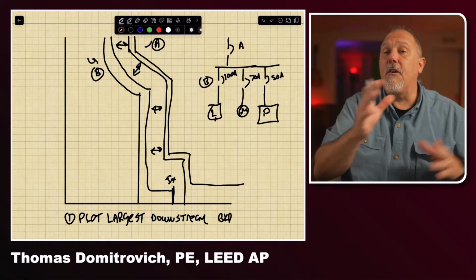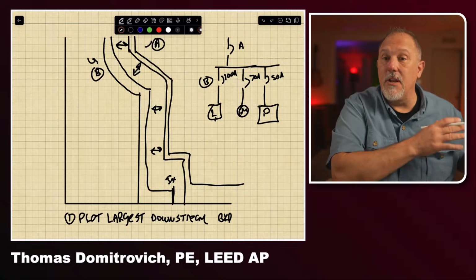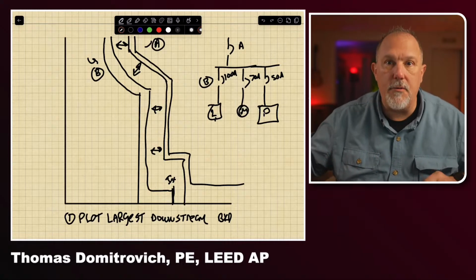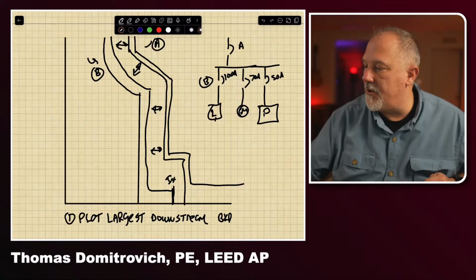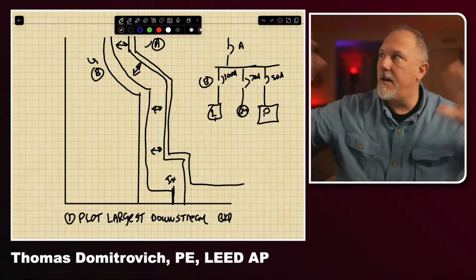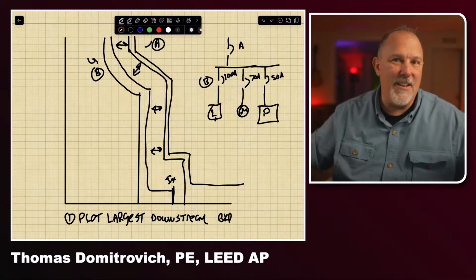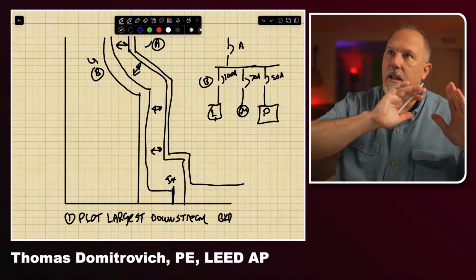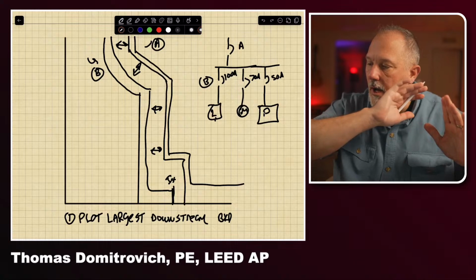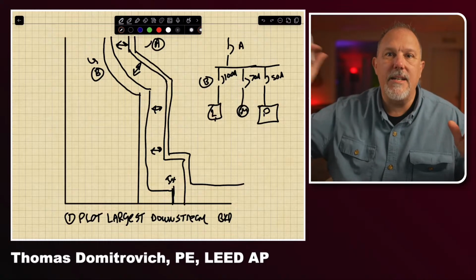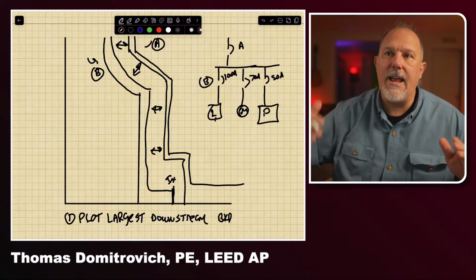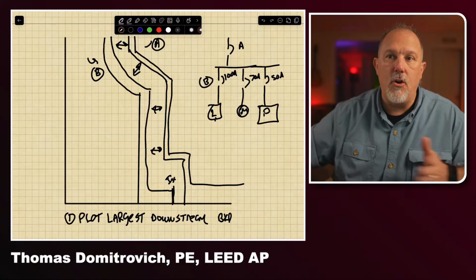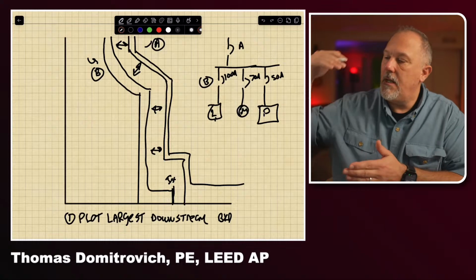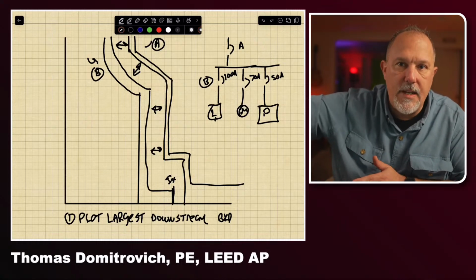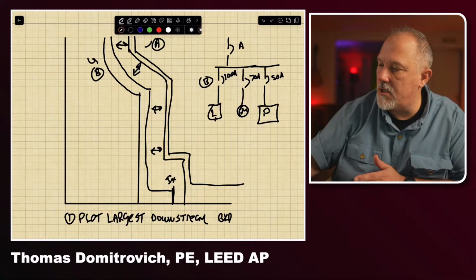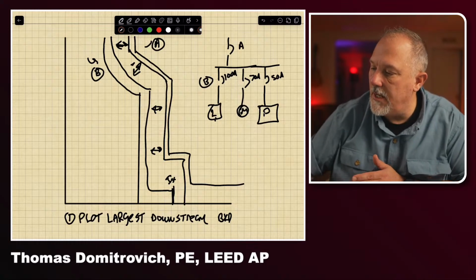Now, for other reasons, you're going to want to take a look at your loads to make sure that you don't overload the circuit, okay? But if I have a 100 amp branch circuit feeding 100 amps worth of lighting loads, if that would ever happen, my conductor is sized for 100 amps. If I add too much load, then my overcurrent device is going to open. What I don't want is my upstream feeder to open in the overload region. So hence I want the separation upstream.